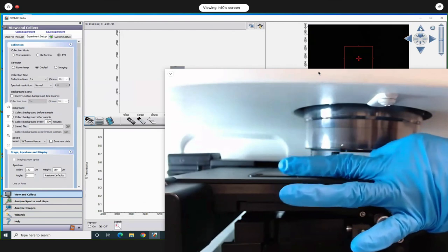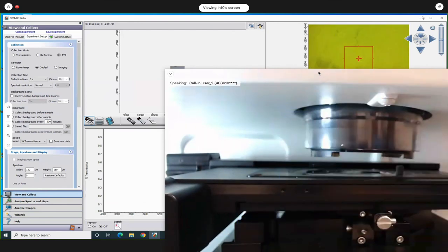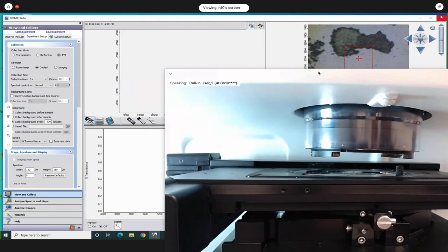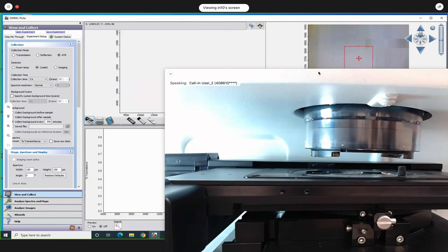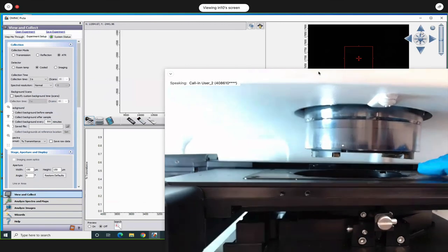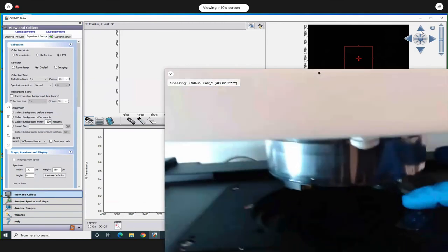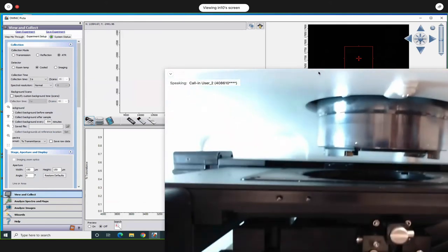So be sure to keep it outside completely when you are doing the alignment. The alignment process by itself can take more like 4 to 5 minutes. When it does that, what we're trying to ensure is that the beam can just go right through. So basically there should be nothing in the beam path. Keep your stage position to home, or basically the center. That is what it will do, so that the beam is just going through the center of it. And then it will do the rest of it.